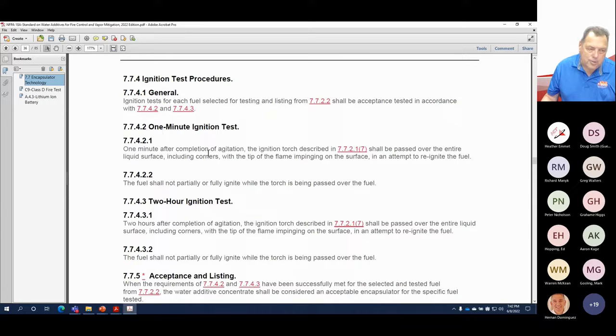There's a 1-minute ignition test after the agitation, but then you have to come back 2 hours later and put the torch to it, and it can't ignite after 2 hours. At first blush people think this is a fuel neutralization test. No, we're using the fuel to demonstrate: does this agent create spherical micelles? Are those micelles capable of encapsulating the fuel? And is that encapsulation stable in high heat over an extended period of time? Hence a 1-minute and 2-hour ignition test.